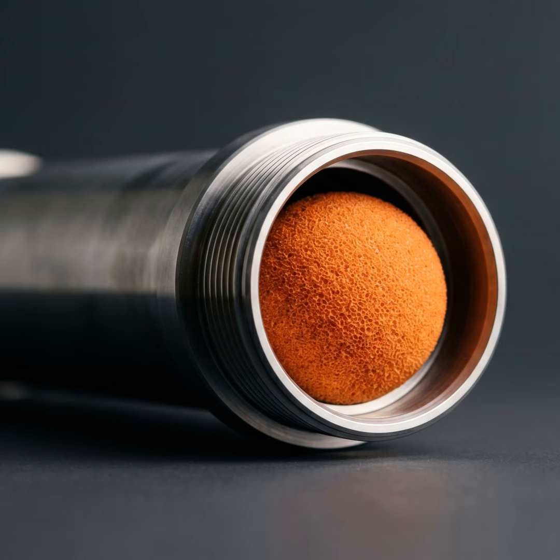And the benefits extend far beyond just energy efficiency and lower utility bills. There are profound long-term mechanical benefits to implementing VFDs. Oh, because it's not slamming on and off. Exactly. Remember the severe physical damage caused by the frequent on-off cycling we talked about earlier? The massive torque spikes tearing up the belts and bearings? Right, the violent shudder every time a giant fan kicks on.